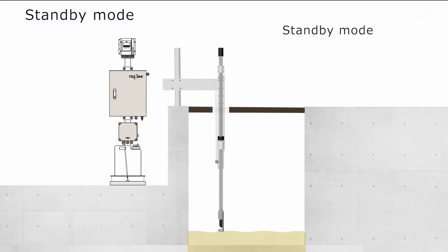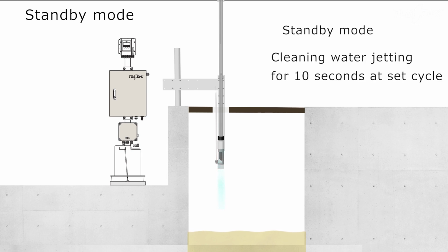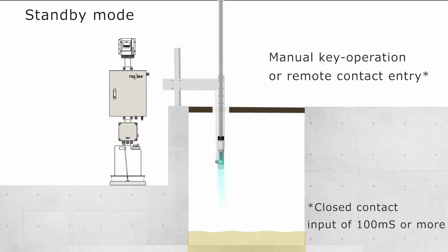This is the third feature. Due to a shutdown of the factory's effluent line, there may be a period in which the water surface drops and the electrodes are exposed. In such cases, you can put it into standby mode. In the standby mode, cleaning water is ejected periodically to prevent electrode drying. Cleaning water is sprayed for 10 seconds at the set cycle. Start by manual key operation or remote contact input. This function is convenient when the effluent line in the factory is stopped, etc.